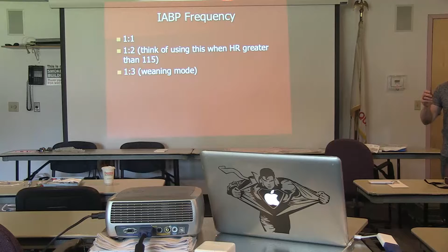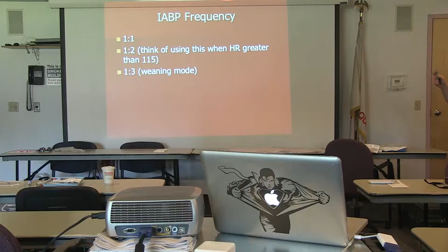1 to 2 we use when the heart is beating so fast that the balloon can't really keep up with it, okay? So that's when the heart rate's greater than 115. And that means that it only inflates every other beat. So if you're at 115, it's only going to inflate like 70-something times. But technically, that should lower your pulse rate. It should help because it's going to increase your stroke volume, right? And then 1 to 3 means it only inflates once every 3 beats, and that's when I'm weaning you off of it. Does that make sense, the trigger sensitivity and timing and all?